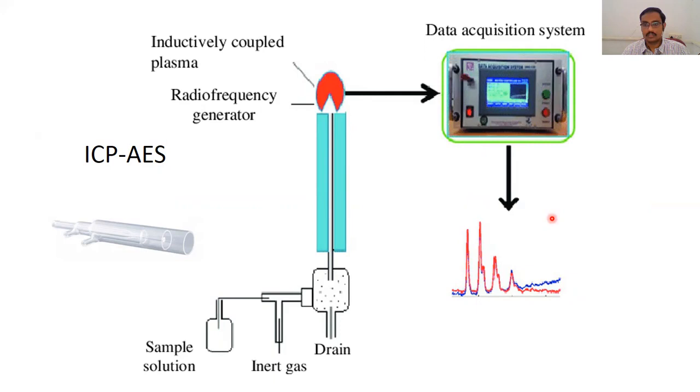So a Bunsen burner or a heat source cannot do it, so you need something more advanced to increase the temperature at which it is excited. So we use what is known as an ICP torch and this ICP torch inductively coupled plasma torch produces plasma which is of a great temperature 10,000 degrees centigrade can be reached in an ICP torch mechanism. And what is this ICP torch?